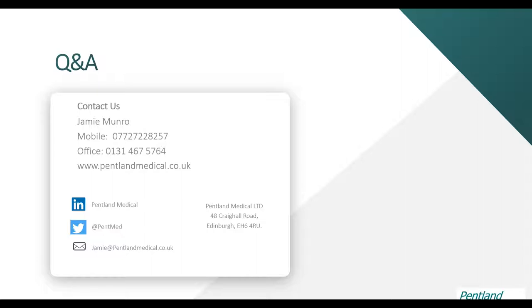Using a Monidrop with a gravity line is more accurate than having nothing on, because without monitoring the administration set visually, you can't tell if it's within accurate limits - you'd have to calculate the drops. That's where the Monidrop is really beneficial.